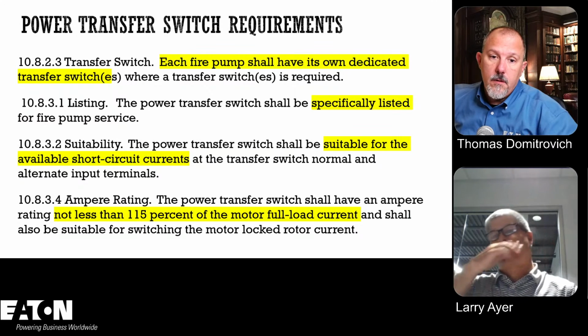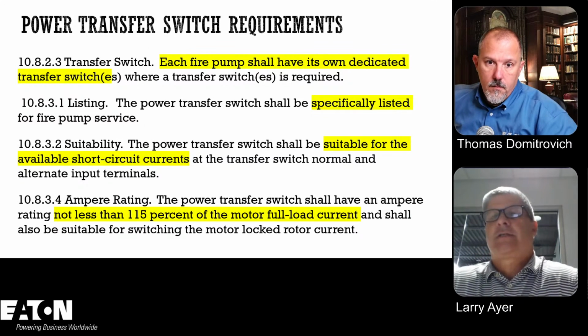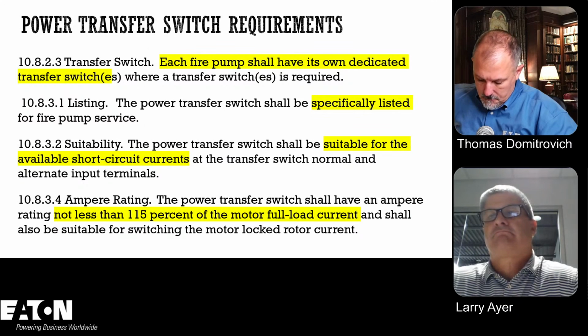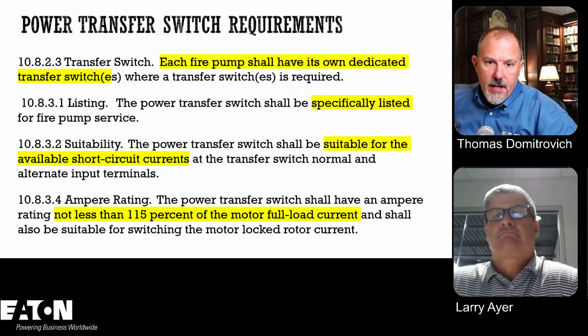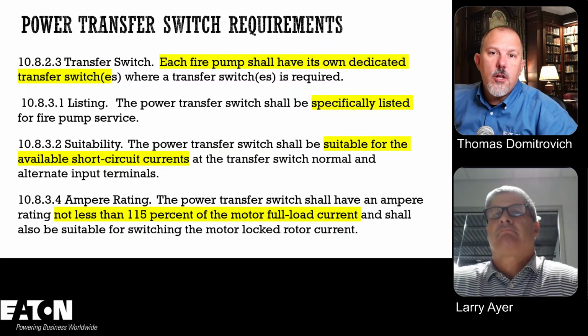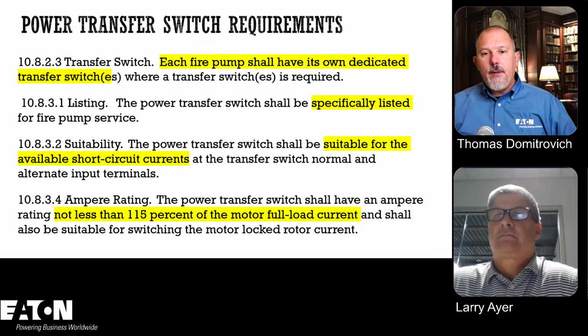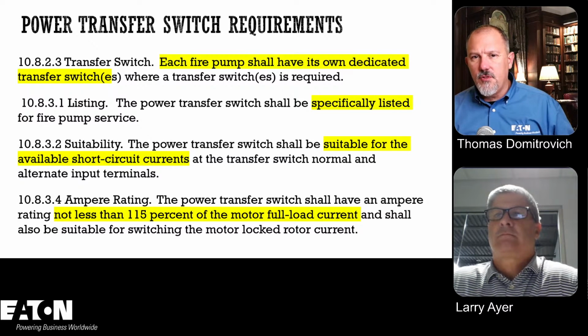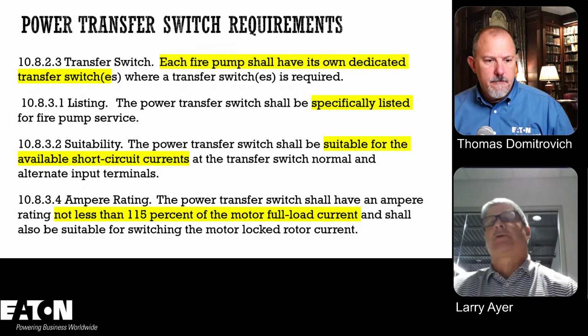Right? I think that this does not have to be rated for locked rotor current. But 10.8.3.4 says, and shall also be suitable for switching the motor locked rotor current. So you don't size it per the locked rotor current, but you do have to be sure of the withstand close-on rating, I guess you would say, and the short circuit current rating, because whenever I think of switching, I think of the withstand close-on ratings, but I'm not sure if that's accurate for a transfer switch. You have to be able to switch the locked rotor amps. At least that's what that implies. I would assume so. Yeah.